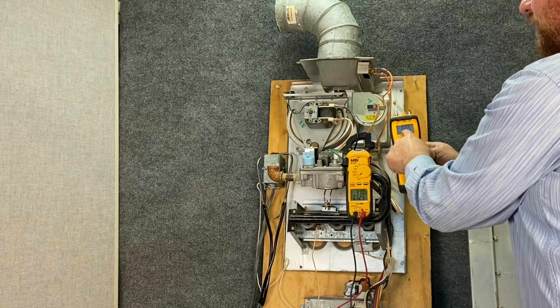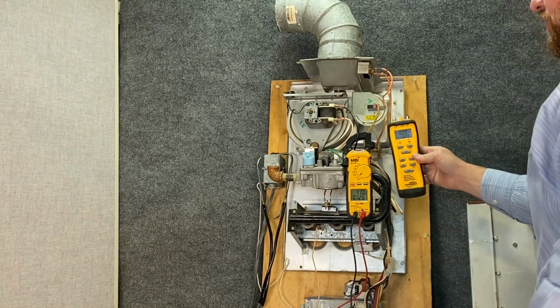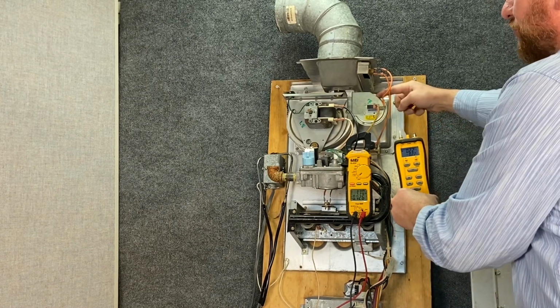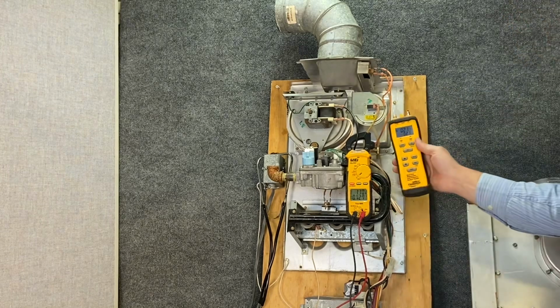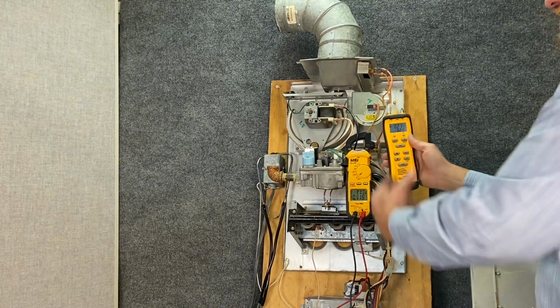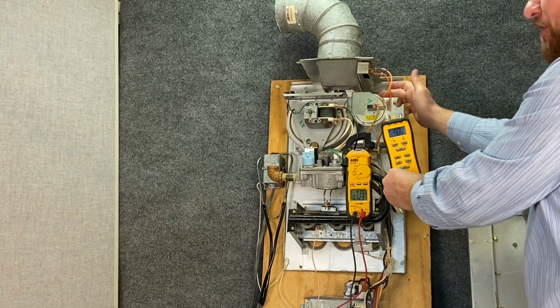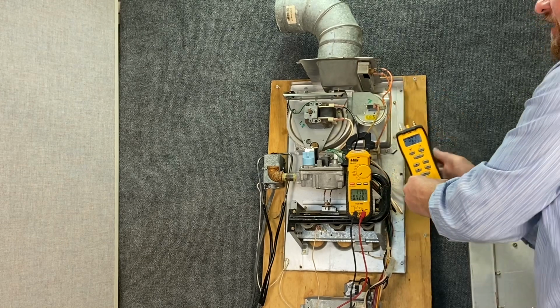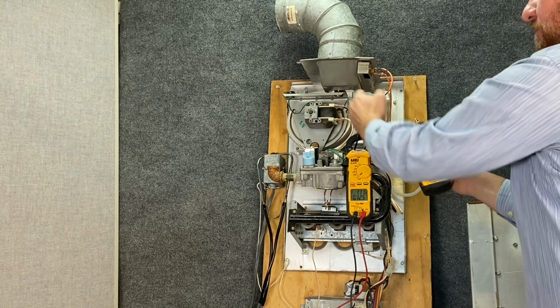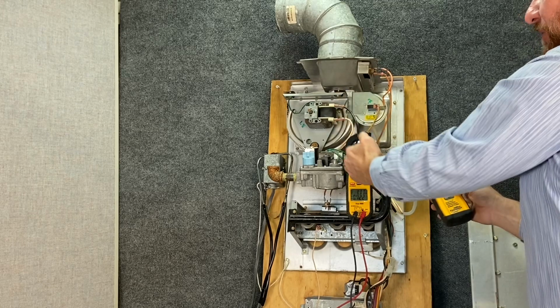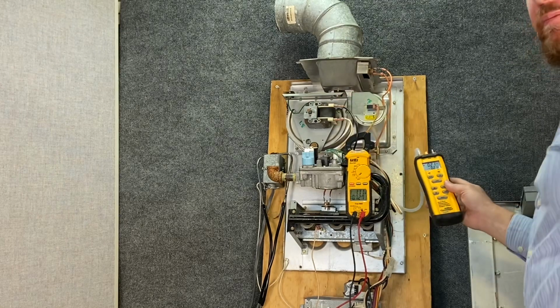And we're pulling 0.22 inches of water column. This pressure switch closes at 0.2 inches of water column. So we are pulling just enough vacuum to the pressure switch for the pressure switch to close. So we are pulling enough of a vacuum with our motor. We have the proper amperage without overamping, and we have the proper voltage.